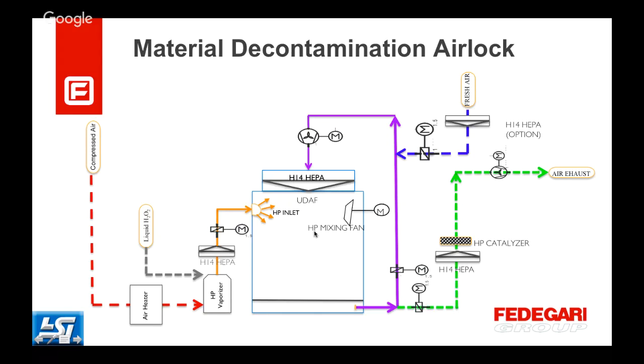Then after the hydrogen peroxide passes, it vents into the exhaust so that no pressure builds up. And we have a HEPA filter, in case of electric breakdown, to protect the content of the enclosure from possible contamination. When we need to start with the aeration, we close this valve from the vaporizer, then we open the fresh air valve, and we have a single pass airflow system with an exchange rate of about 200 chamber volumes per hour, and then exhaust through a catalyzer, and then to the atmosphere.